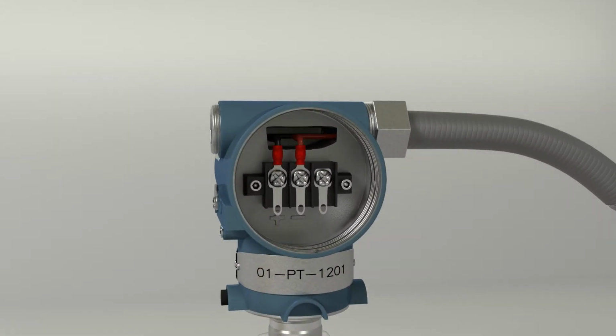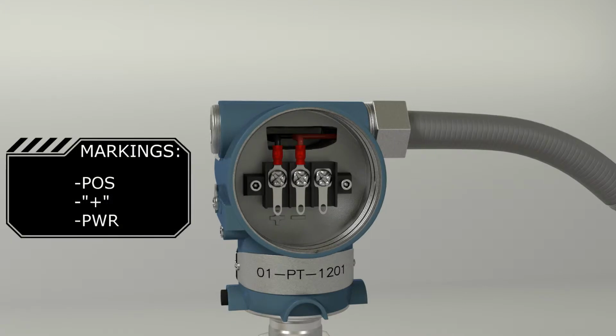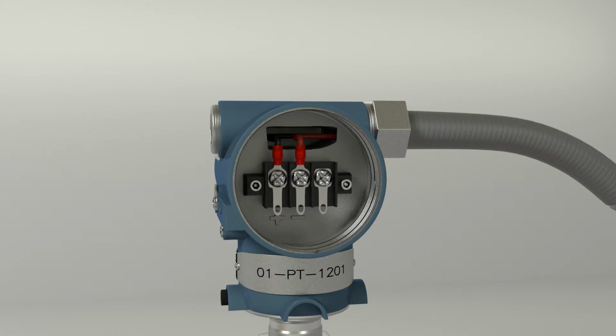Now looking at the transmitter, you will see that there are two wires connected. You should be able to see some indication that one of the terminals that the wire goes to is positive. It will have some indication that it is a positive terminal. This could be a plus symbol or the letters POS or anything like that. We're going to move this wire first. The power for the two-wire pressure transmitters is 24 volts DC. This means that you can touch the wires and they will not hurt you at all.